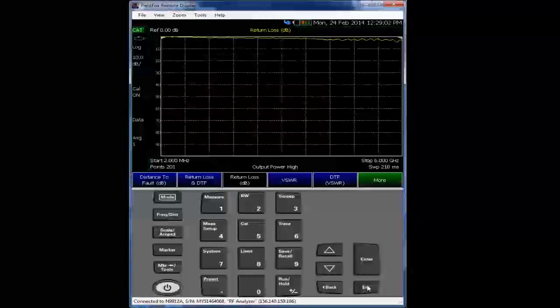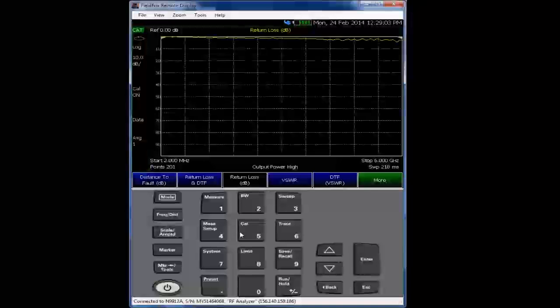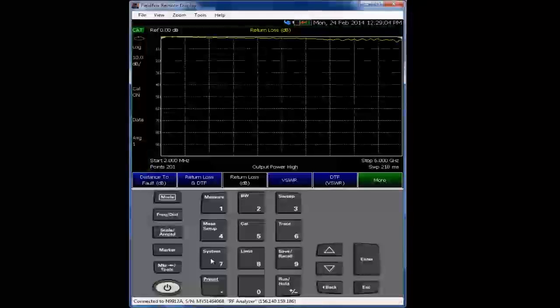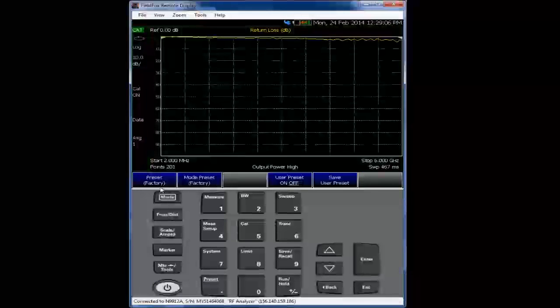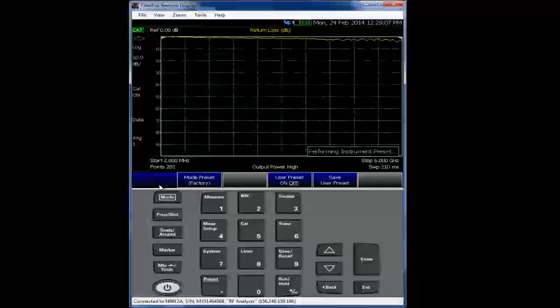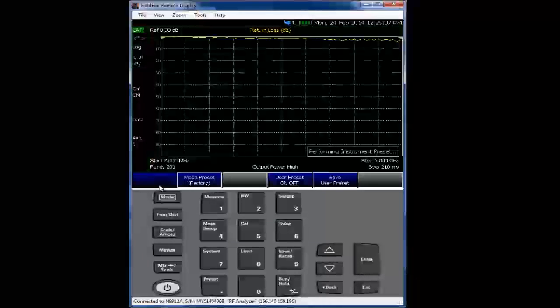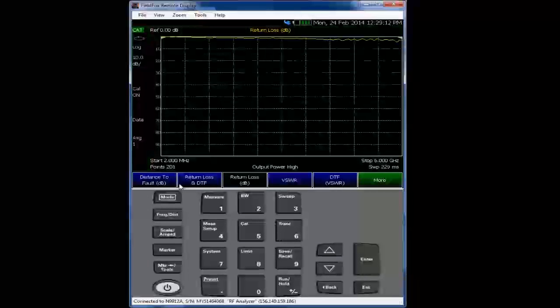So the first thing we'll do here is we're going to perform a preset on the FieldFox. We'll then enter into the spectrum analyzer mode.